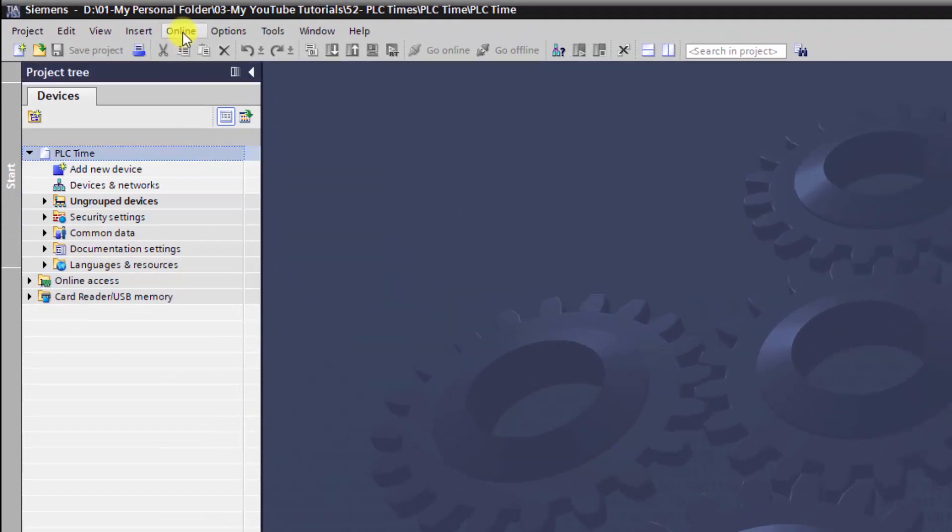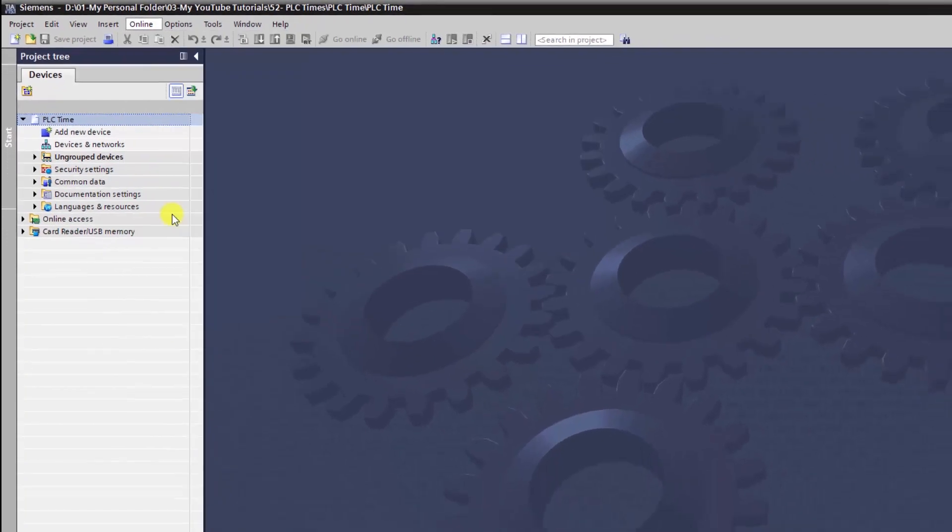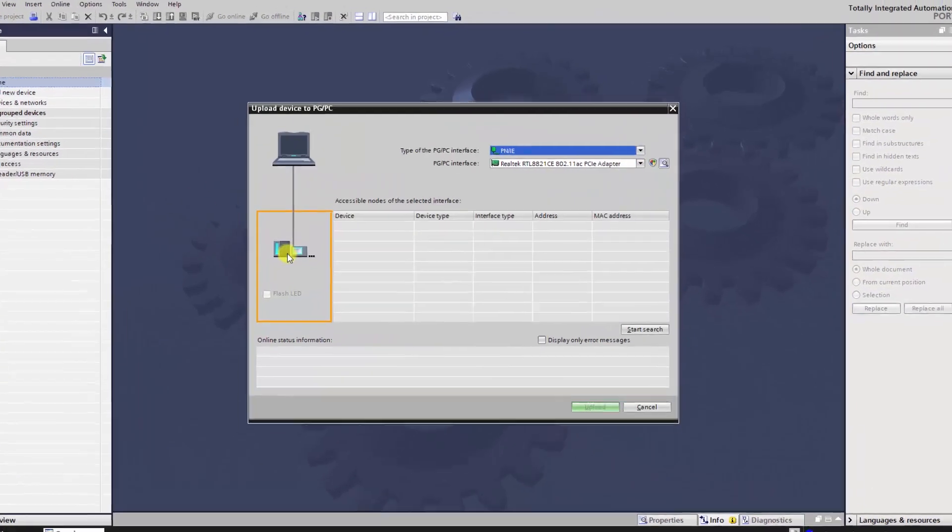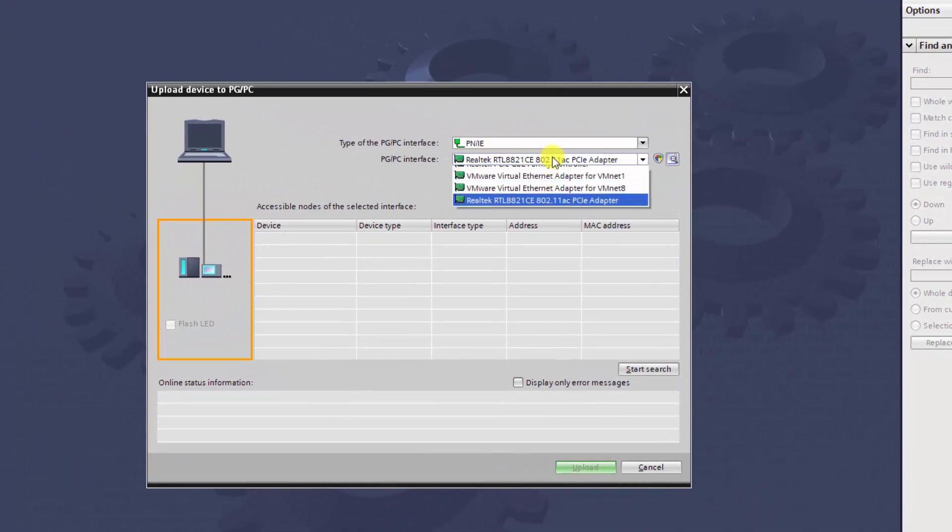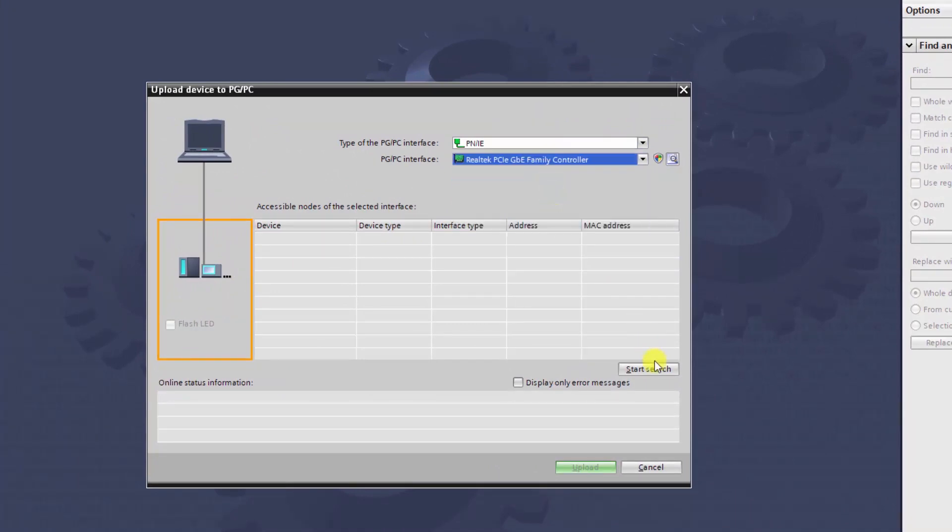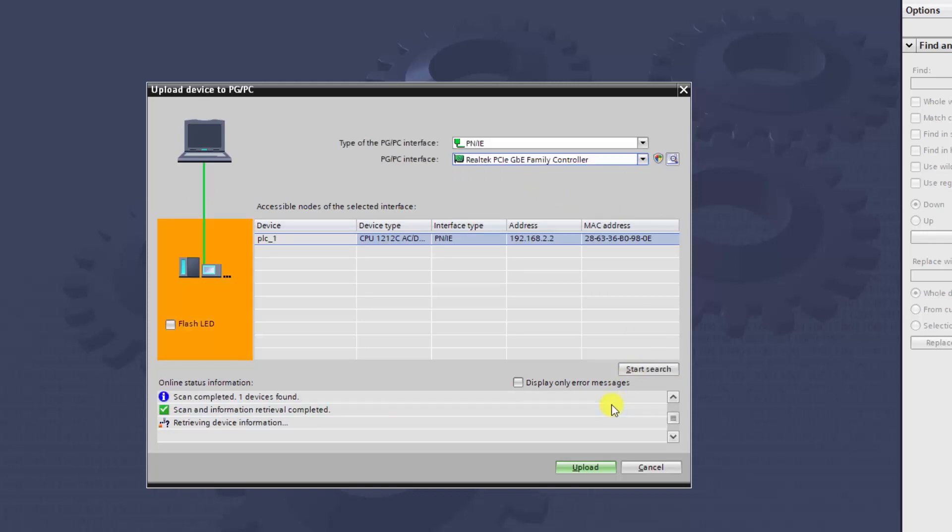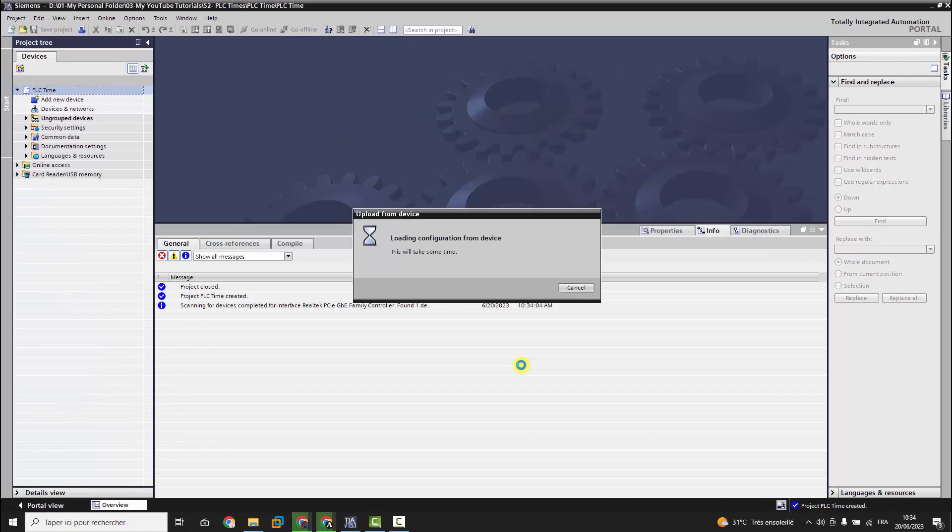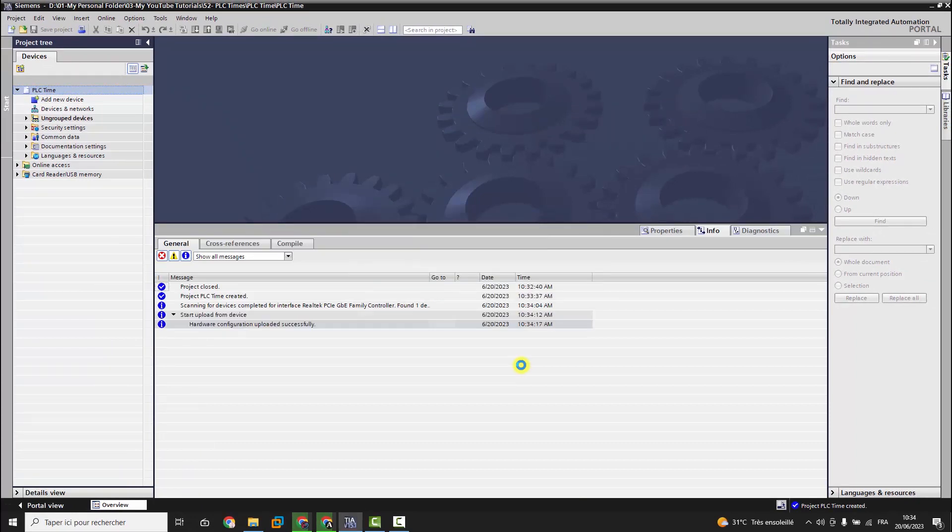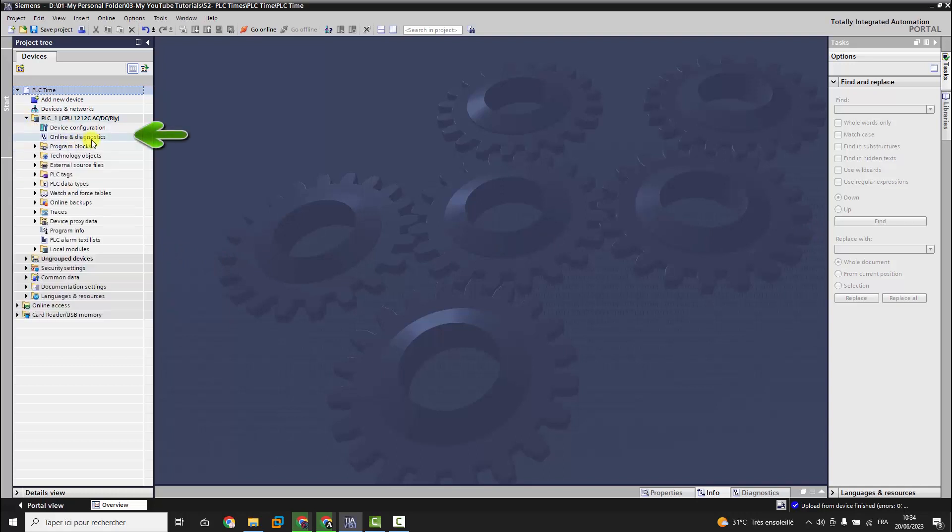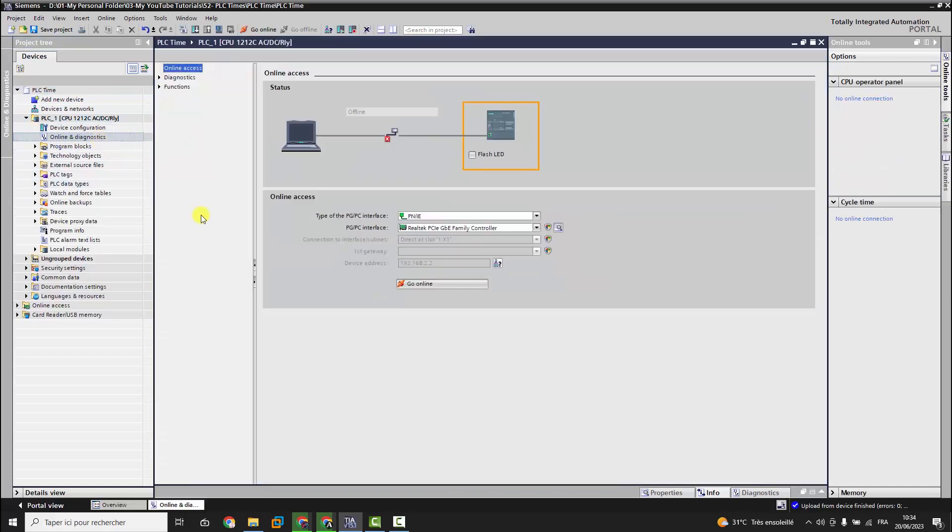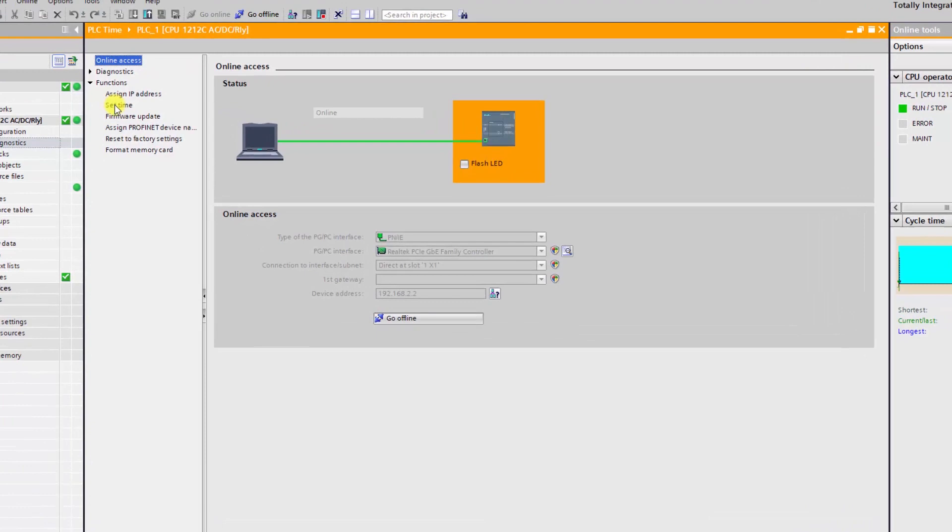We create a new project. We click once on the name of the project, and under the top menu Online, we choose Upload device as a new station, hardware and software. Through the PG/PC interface, we choose the PC network card as interface and click on Start Search. Once the online PLC is found, we click on Upload.